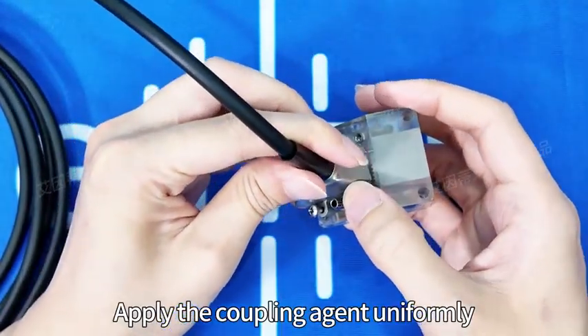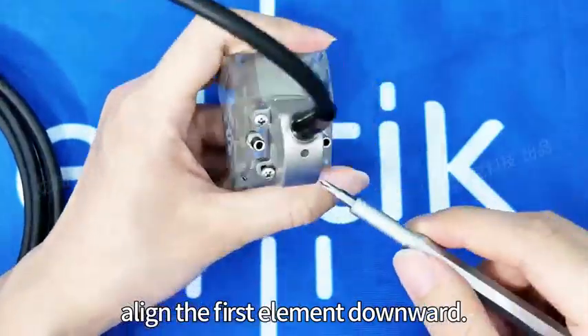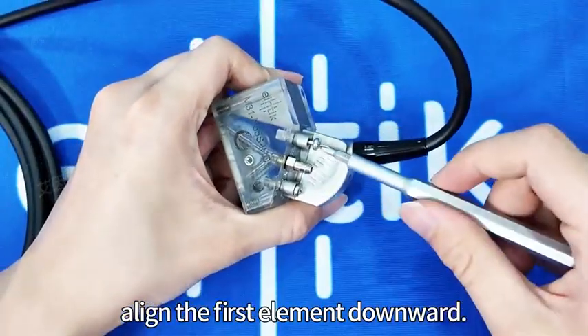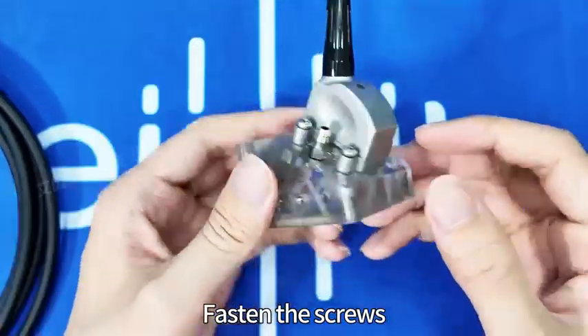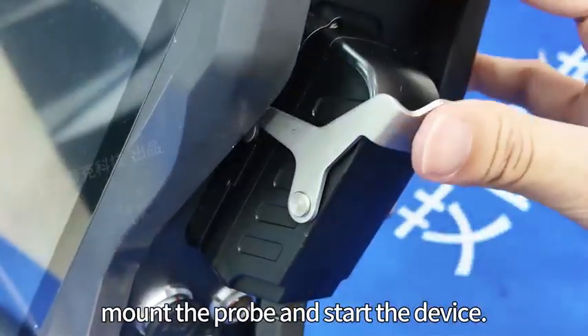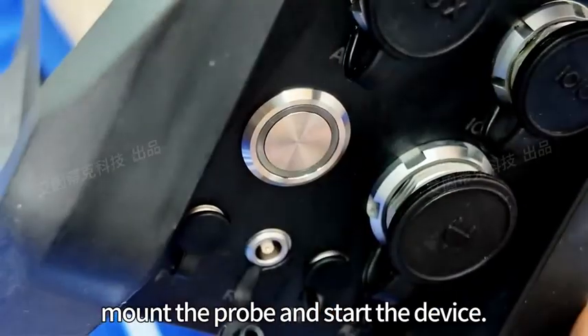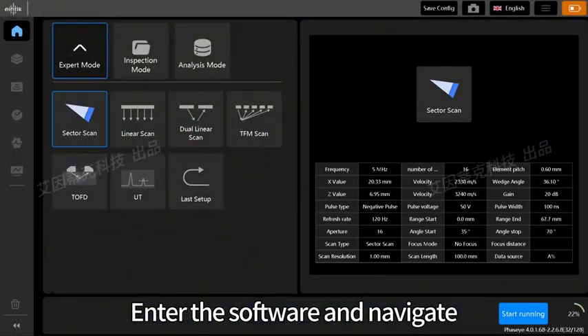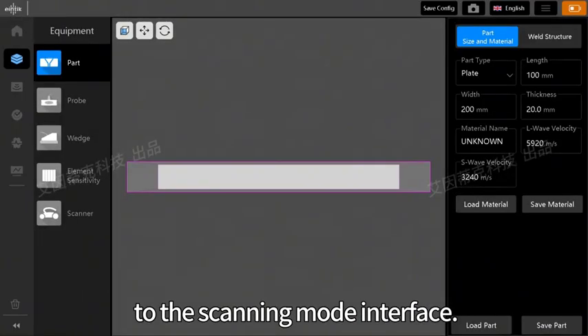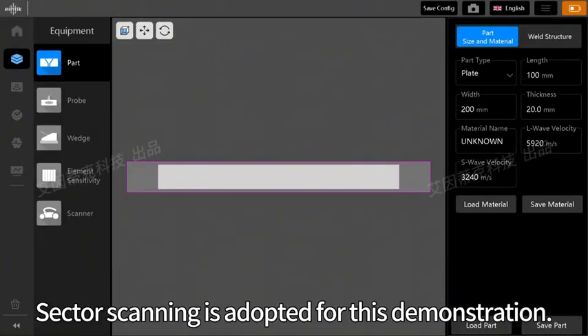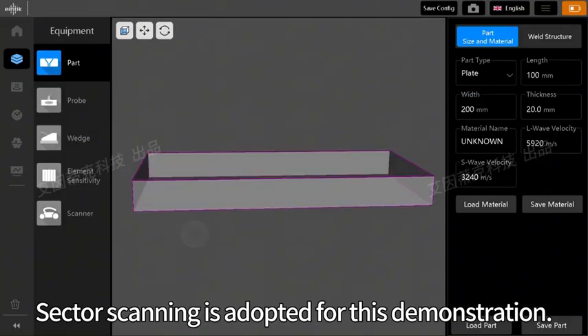Apply the coupling agent uniformly. Align the first element downward. Fasten the screws. Mount the probe and start the device. Enter the software and navigate to the scanning mode interface. Sector scanning is adopted for this demonstration.